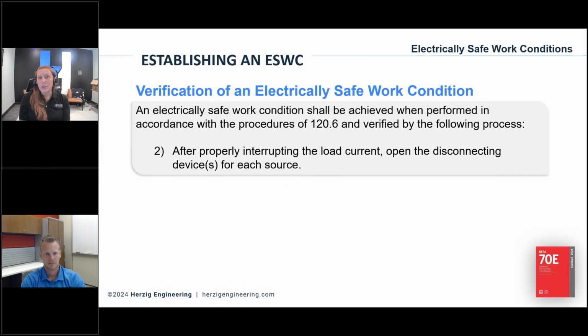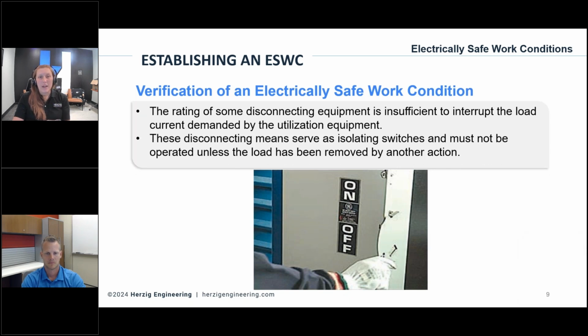Okay, step number 2 is kind of 2 separate steps in my opinion. You properly interrupt the load current and then you open up the disconnecting devices. All right, we want to shut the equipment down. The motors need to stop drawing current, and whatever loads you have need to be turned off with the proper controls, push buttons, switches, whatever. And then you go open up the breaker or the disconnect point, because the rating of some disconnects are not designed to interrupt that load current.